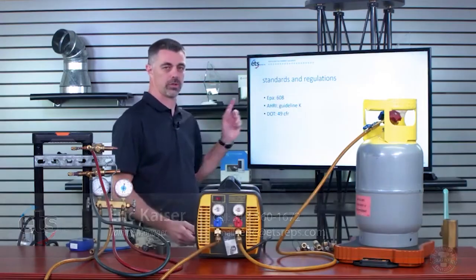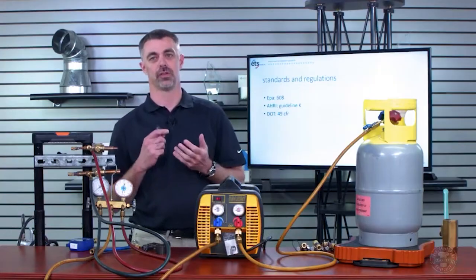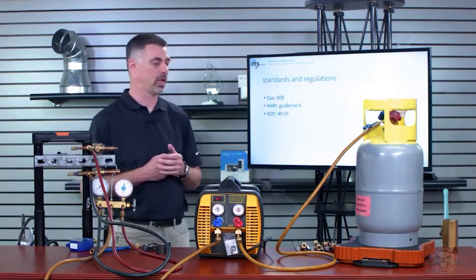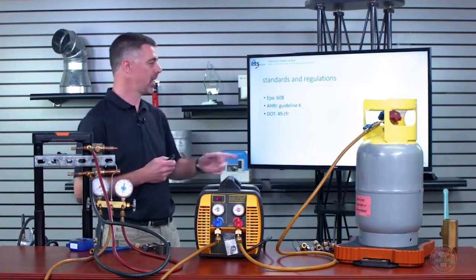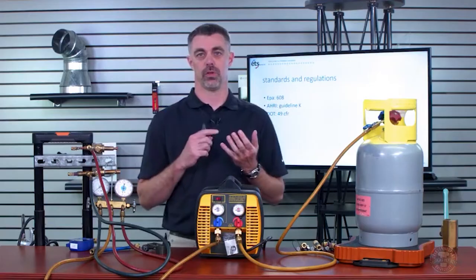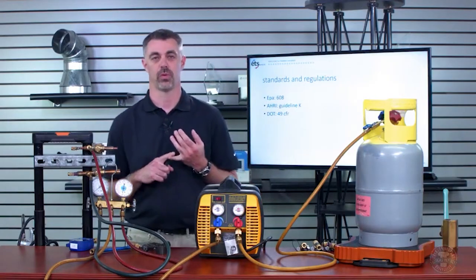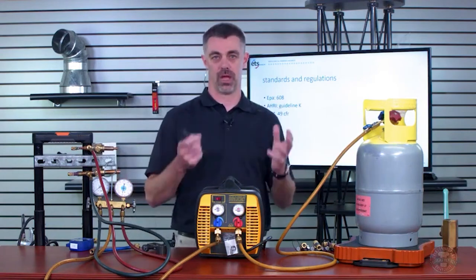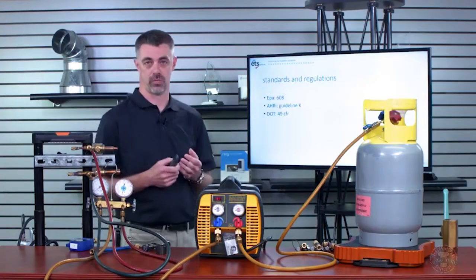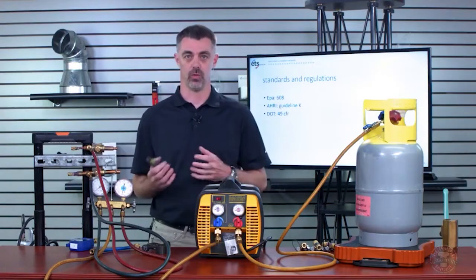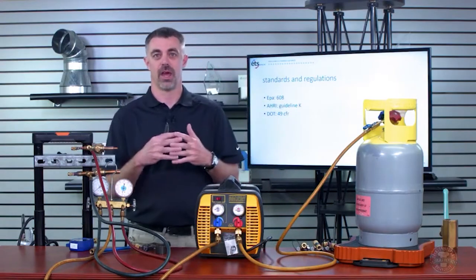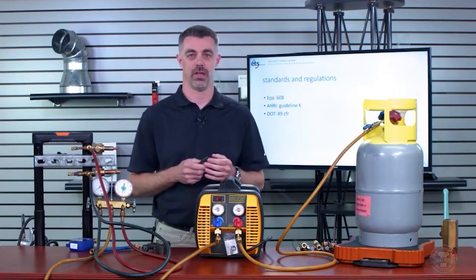With refrigerant recovery, technicians deal with standards and regulations from three places: the EPA with Section 608, AHRI Guideline K, and the DOT's 49 CFR. The DOT rules are specific to transportation — when we put tanks in our trucks and drive them down the road. The EPA governs when we need to recover and how much we can lose during recovery. We need to figure out how all three intermesh and where to apply each.